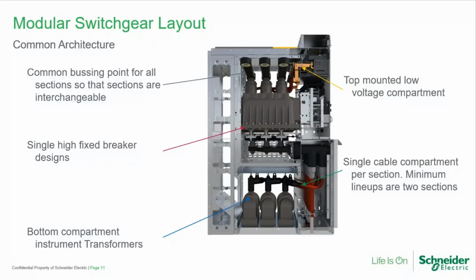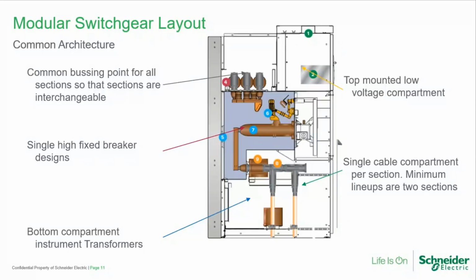So if I look at this image of the solid insulated switchgear I was showing you, you can see busing on top, circuit breaker below that, instrument transformer compartment in the very bottom, and then that operating mechanism, low voltage box, and cabling on the front of the switchgear. If I do a similar comparison for gas insulated switchgear, you can see it lines up very, very similarly. So when you're using these modular designs of switchgear, it's very easy to design the layouts because of all these common points for bus connection, cable connection, and operating equipment.